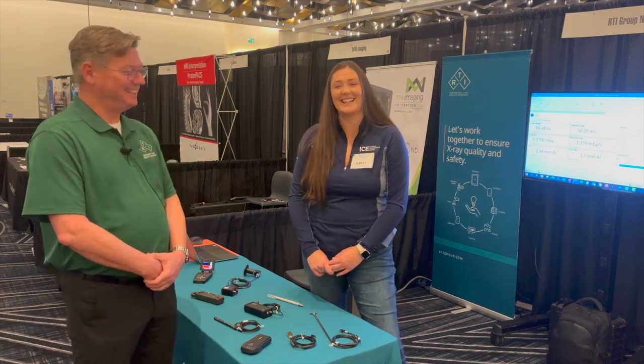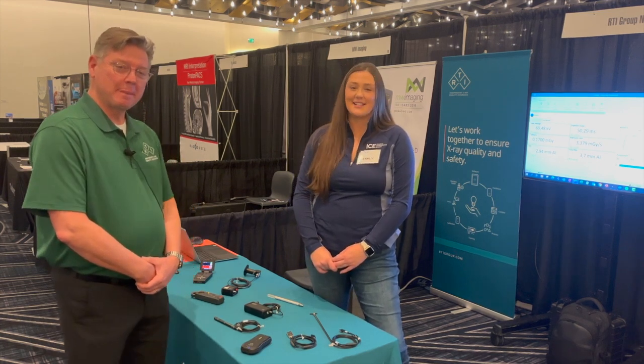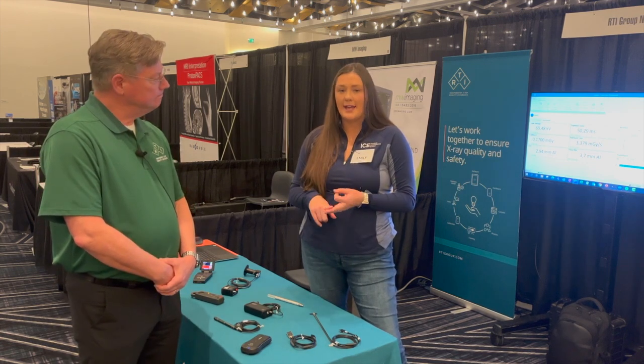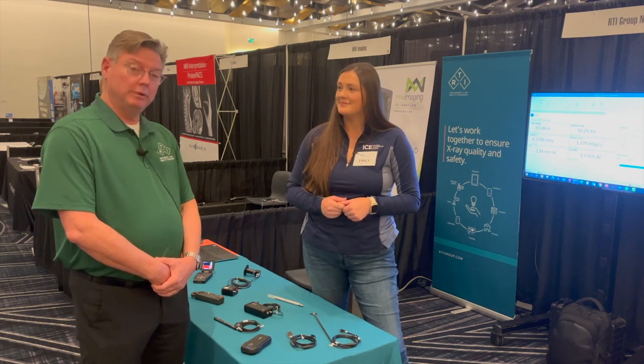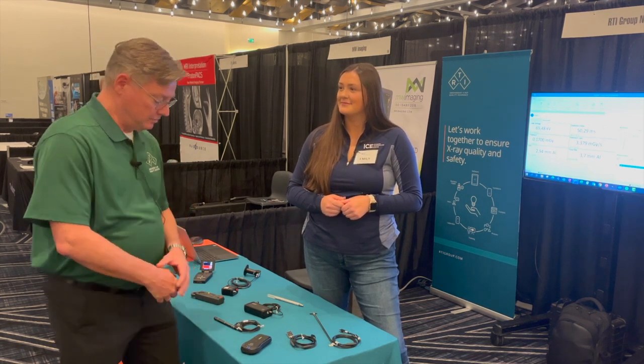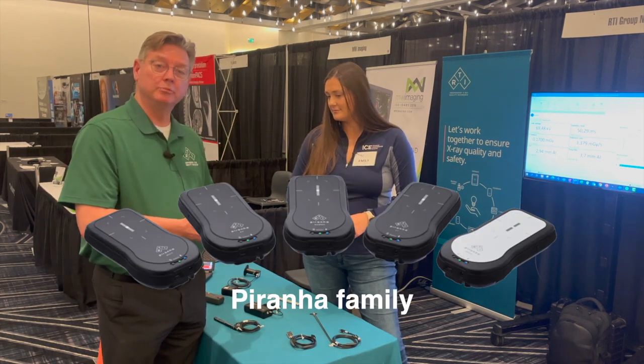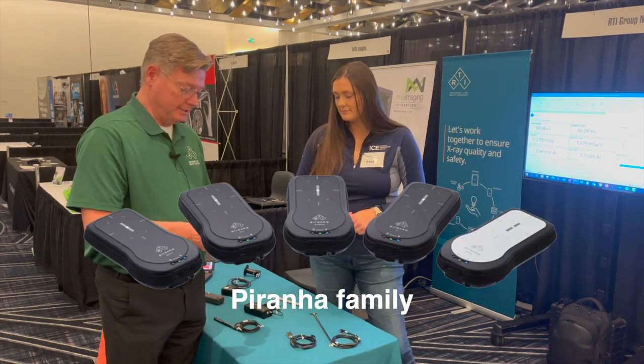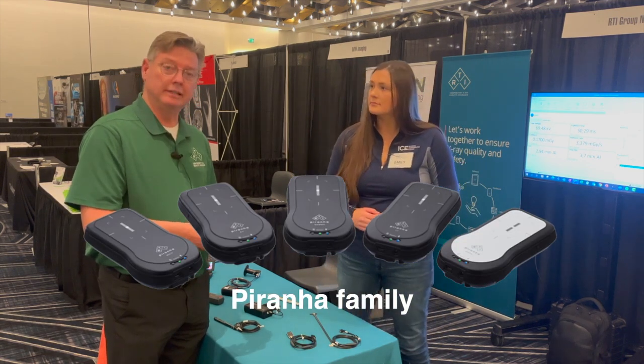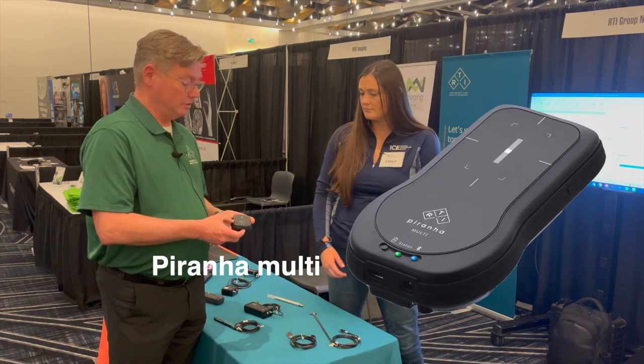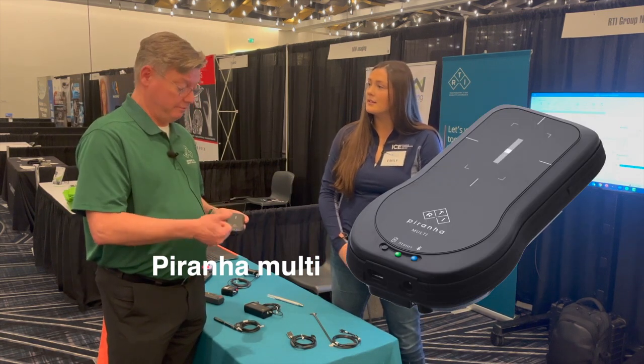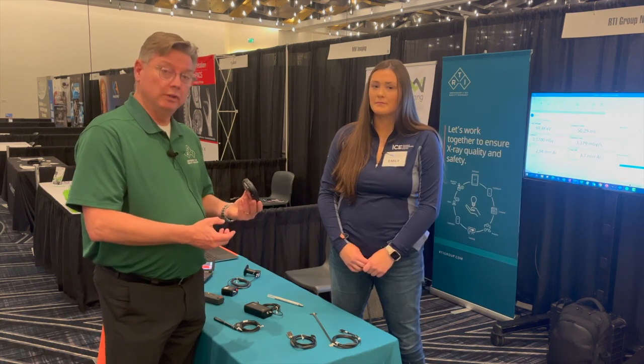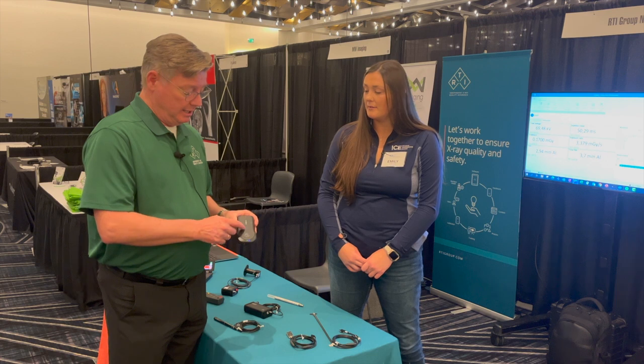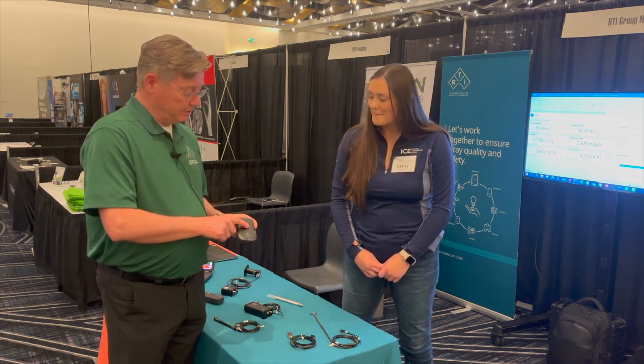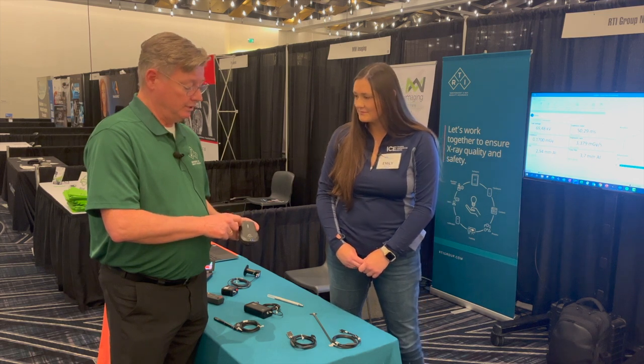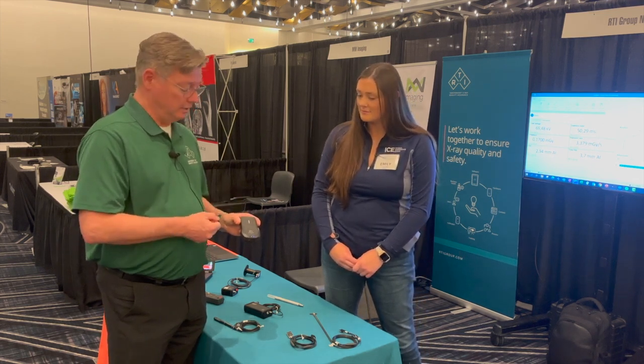It is, yes. Can you share some highlights of RTI's X-ray test solutions for CT, mammo, RADF, and even dental? Yeah, sure. We've got a range of products, and what I'd like to start with is the first one, the flagship, which is the Piranha. The Piranha is a multi-modality instrument. This one I'm showing is a Piranha Multi. It does everything from mammo, RF, CT, dental, all in the one unit. Wow. The detector area is this white area here, and from there you can get KV, dose, time, total filtration, and HVL all in the one shot.